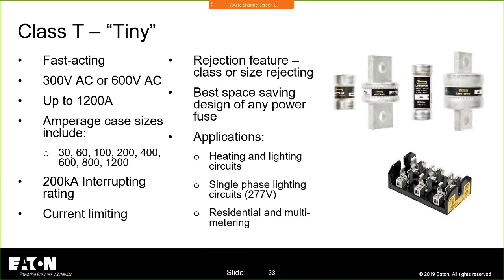T, class T is for tiny. That's how you remember. They're smaller fuses. They go up to 1200 amps, but they're not as big as those big class L fuses. They're 300 volts or 600 volts, up to 1200 amps: 30, 60, 100, always up to 1200, 200,000 amp interrupting rating. Current limiting, rejection features. They've got rejection features, space saving because they're smaller. You'll see these on heating and lighting circuits. You'll see these actually in residential as well, service entrance type equipment, where you want that smaller fuse performance.